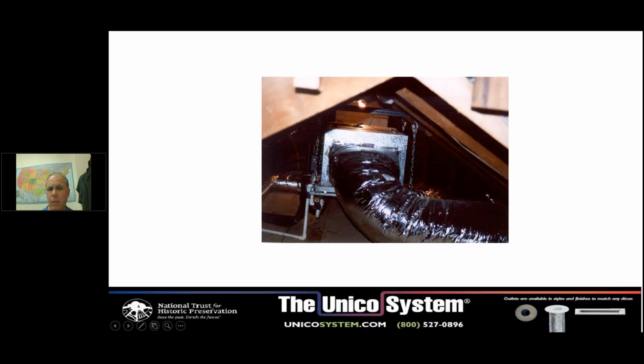There's a drain pan underneath it. This drain pan is galvanized, so it lasts forever, and there's a bar on top of that, so the air handler is actually just at the top of it. If you were ever to have overflow or the system were to get clogged, it would flow into the drain pan, then be trapped and run generally to an outside drain. We generally tell contractors they should run it over something like a kitchen window so you'll see it and know you need to call the contractor out to unplug it. It doesn't happen often, but it can.